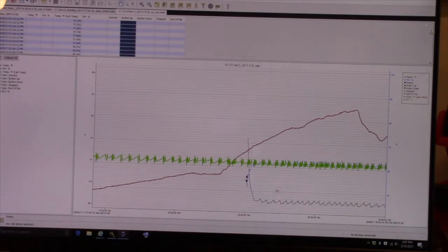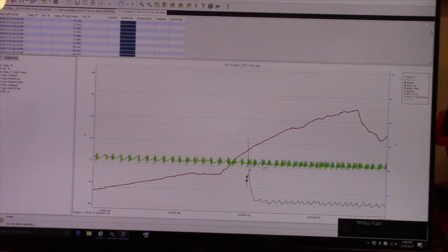Now, the system is constantly trimming itself, so somewhere along the line you have to realize, of course, that you get these micro variances, okay? And the important aspect, though, is that the micro variances aren't really noticeable at all by the tobacco, because they simply happen too quickly. They're like frames on a motion picture. You don't see the individual frames, you simply see them linked together, and because tobacco as a hygroscopic substance actually lags the environment, you don't give it enough time to physically change.